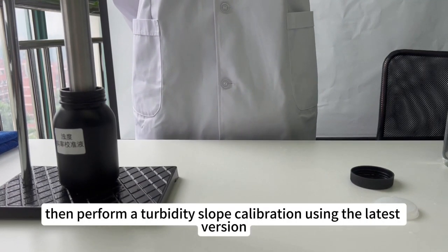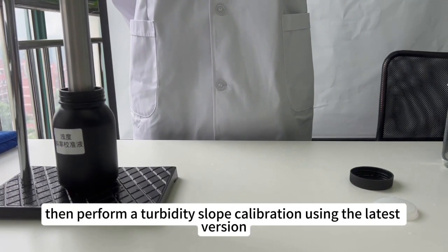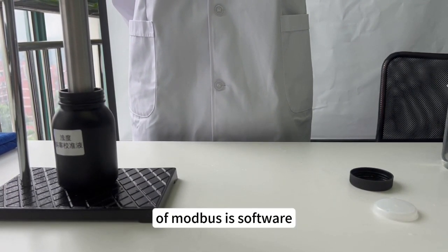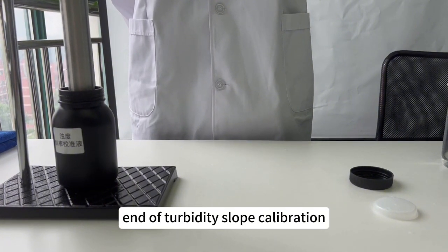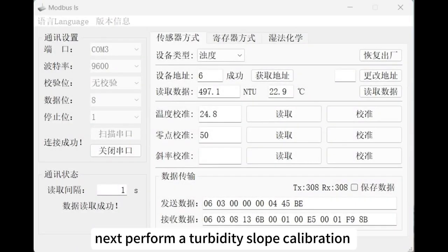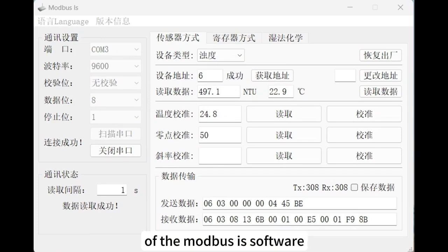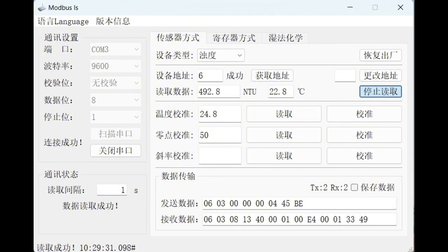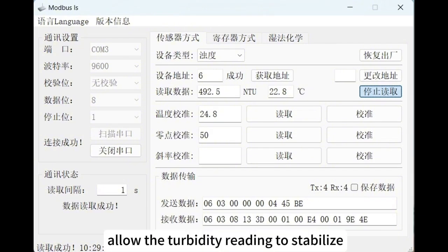Then perform a turbidity slope calibration using the latest version of Modbus IS software. End of turbidity slope calibration. Next, perform a turbidity slope calibration using the latest version of the Modbus IS software. Click on Read Data. Allow the turbidity reading to stabilize.